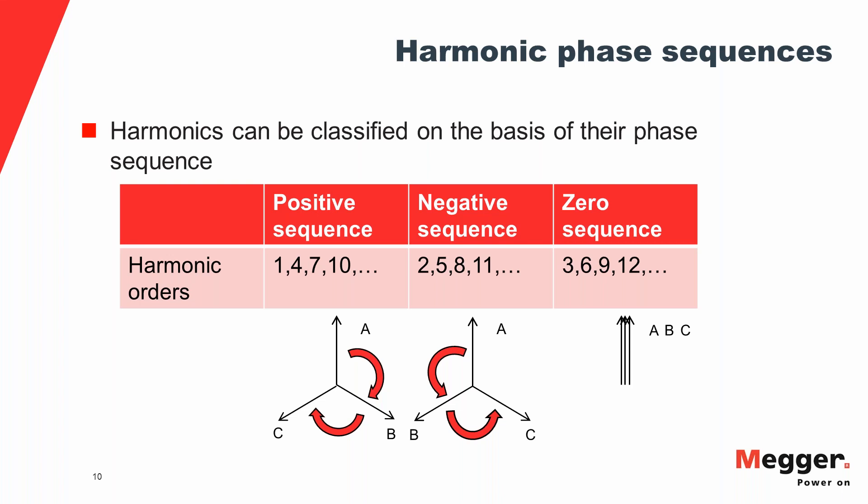Based on phase relationships, harmonics can be classified into three categories. The fundamental, fourth, seventh, tenth, thirteenth, and so on fall under positive sequence. Second, fifth, eighth, eleventh, fourteenth are all negative sequence harmonics. The multiples of the third harmonic — third, sixth, ninth, twelfth — fall under zero-sequence harmonics.